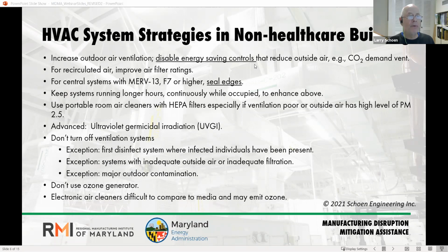Boy, at the beginning when people were starting to hear shelter in place, and does that mean I should turn my air conditioning off? No. If you have a substandard ventilation system that has no outside air and no filtration, then perhaps. But any kind of decent HVAC system that has outdoor air and filtration, you want to run it, with a couple of exceptions. If you did have an exposure to infection, then perhaps you want to clean the system before you turn it back on.